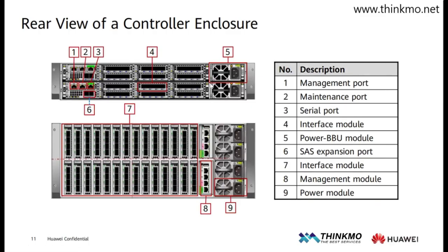As for the fans, we also have a 1+1 setup. The fans are also 1+1 redundant. For these modules that are prone to failure, no matter which one fails, it doesn't affect the system, because we have multiple of each. If one fails, once we identify the problem, we can quickly remove and replace it directly without needing to shut down. This is because all our plugins and components support hot swapping. This is our rear view.